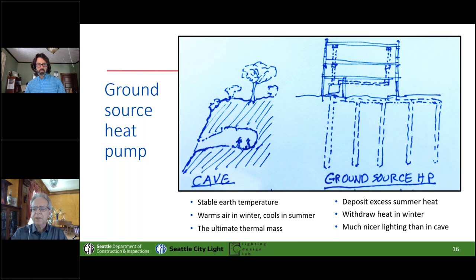A ground source heat pump involves drilling these holes that are usually like 300 feet deep with a U-shaped tube. In a picture, it's plastic pipe that's like an inch in diameter in a U-shape that's pushed down this hole, and the hole's filled up with grout.